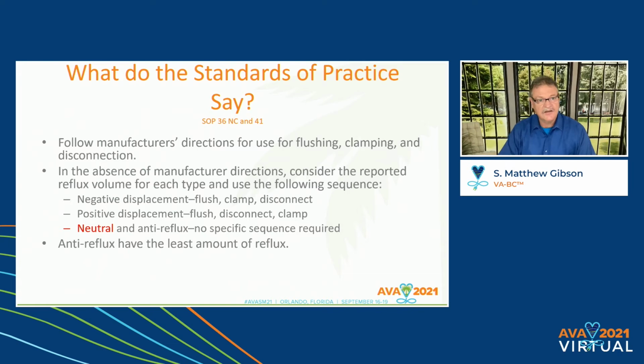A little bit more from the standards. It does say, follow the manufacturer's directions for flushing. However, whenever I went out and looked at the IFUs, the instructions for use, some of them said follow what the standards of practice say. And I'm like, wait a minute. The standards say follow the manufacturer's directions, and the manufacturer says follow the standards. I'm like, I don't know what to do.